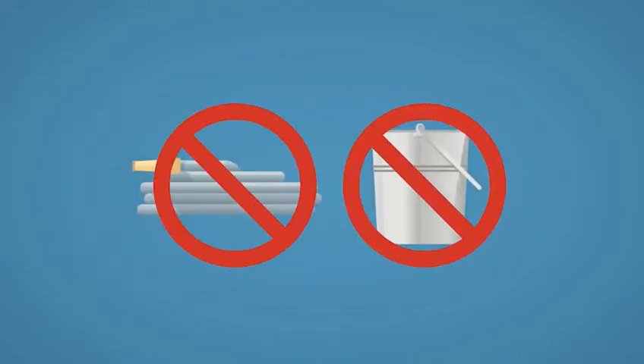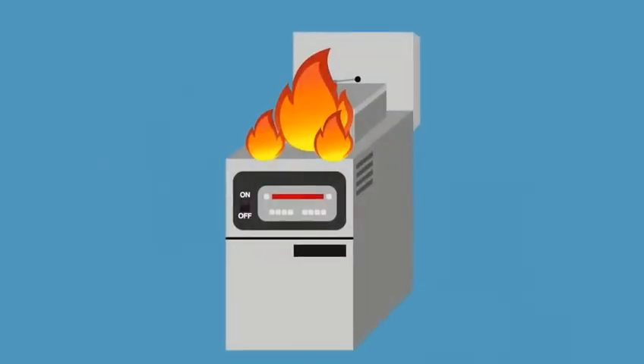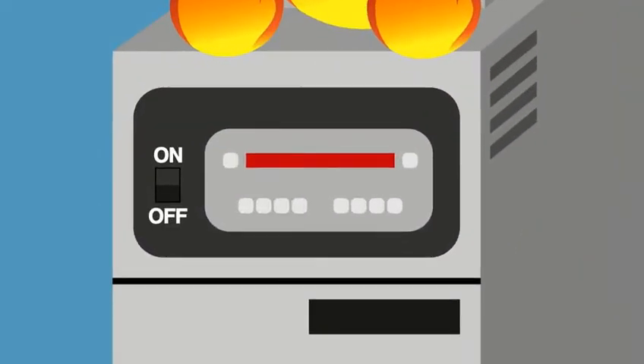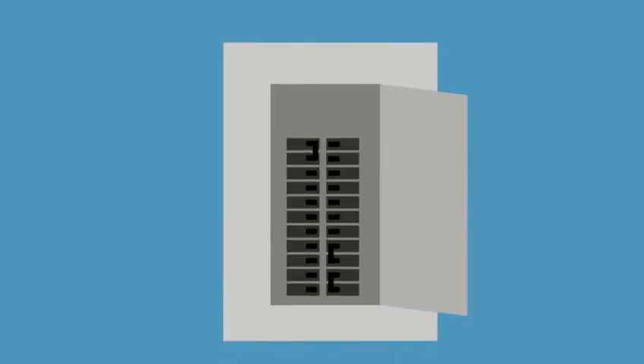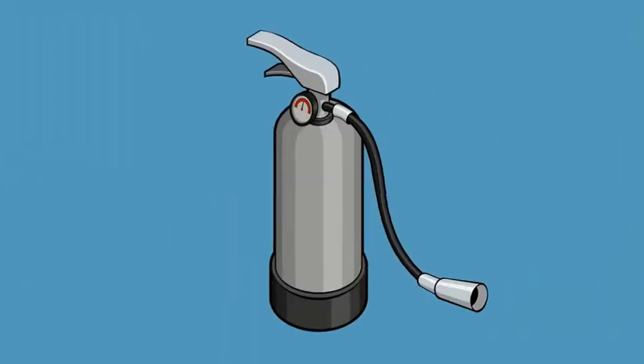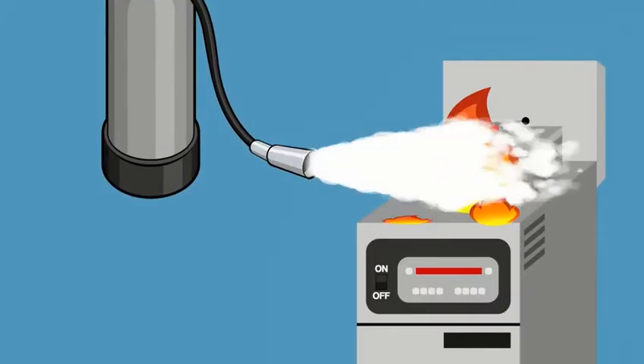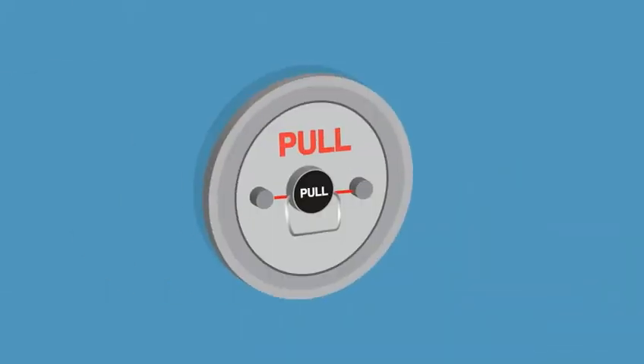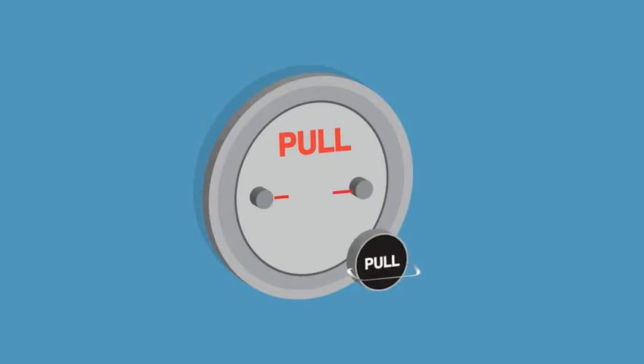And this is important. Never try to put out an oil-related fire with water or ice. If a fire starts in the pressure fryer, power off the fryer. Then unplug it and turn the power off at the breaker. Use a K-class extinguisher and dispense it until it's empty. Pull the manual fire suppression handle if the system doesn't automatically dispense the chemicals.